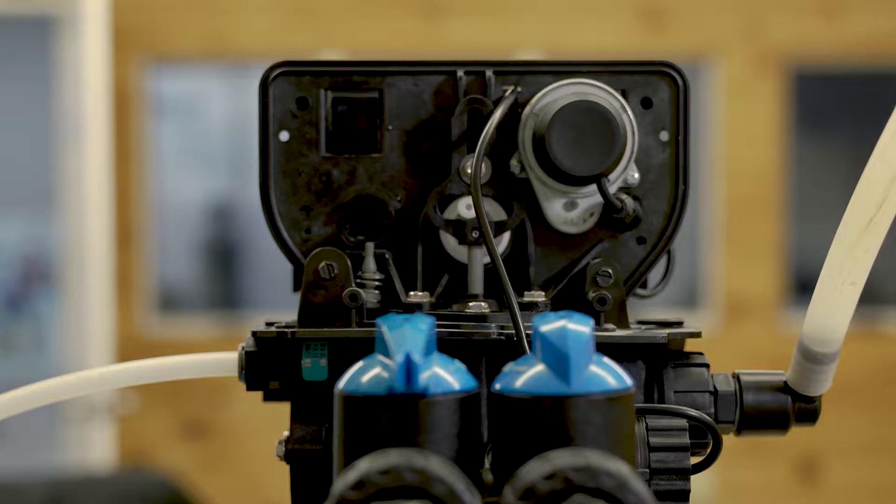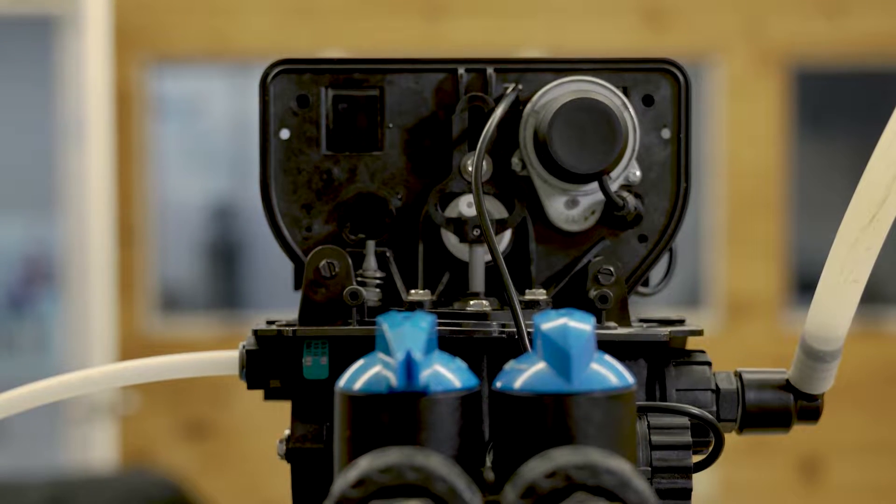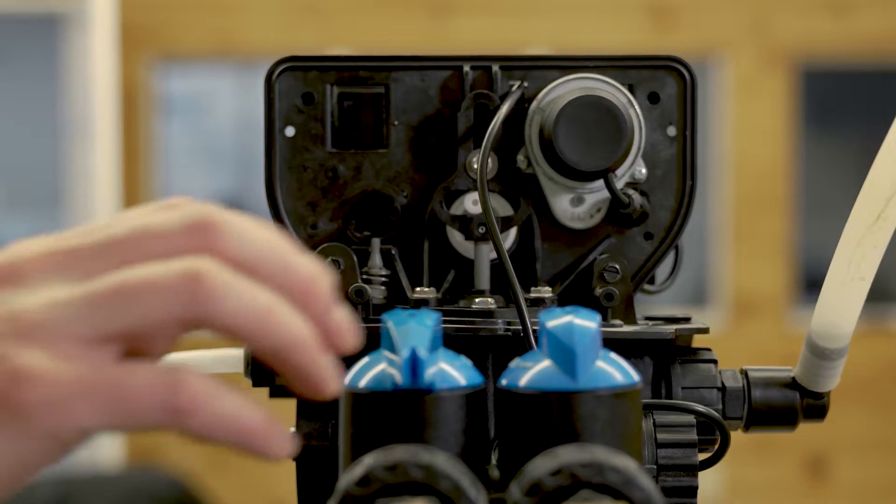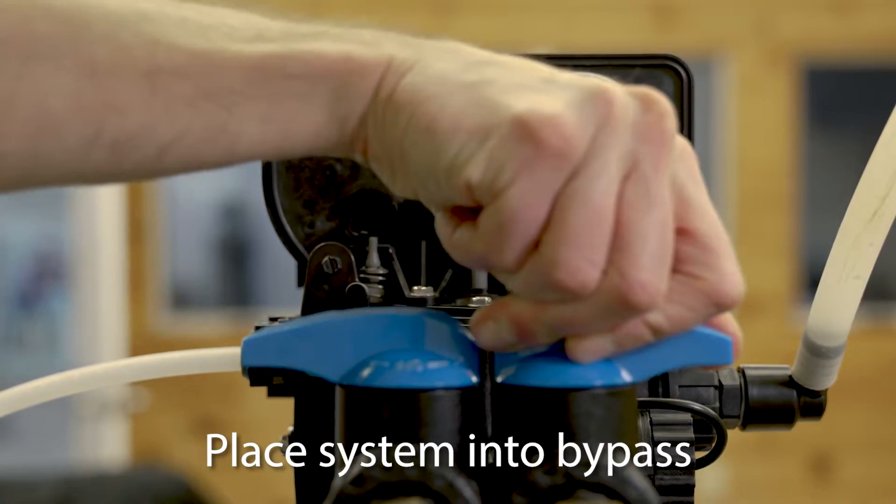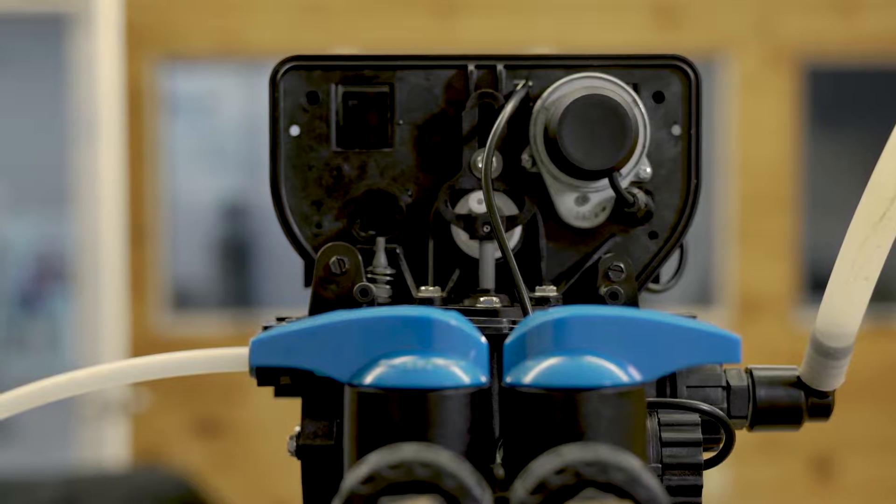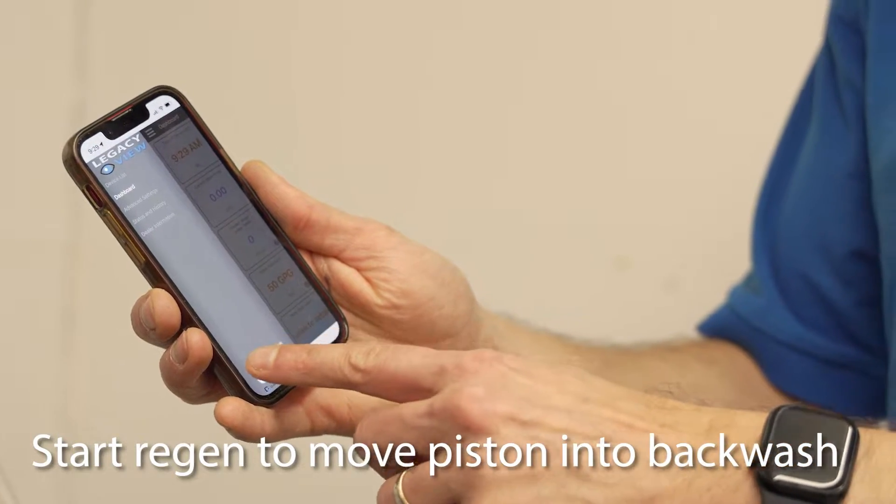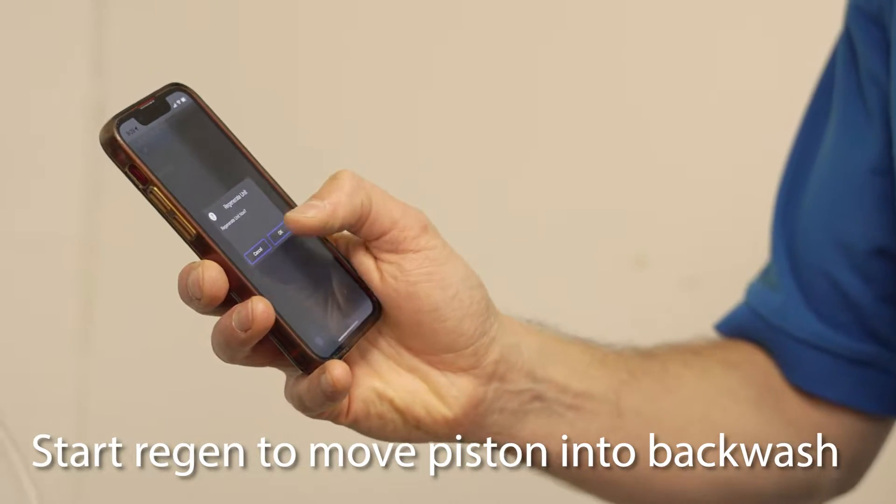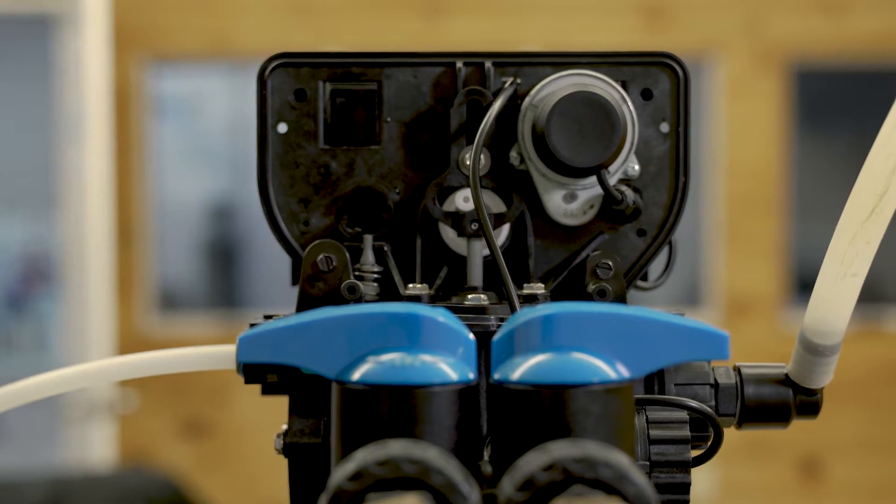Before taking anything apart, we want to take pressure off the system. You can do this by putting it into bypass and then cycling it to backwash by pressing regenerate now in the legacy view app or pressing and holding the set change button on the front of the valve.